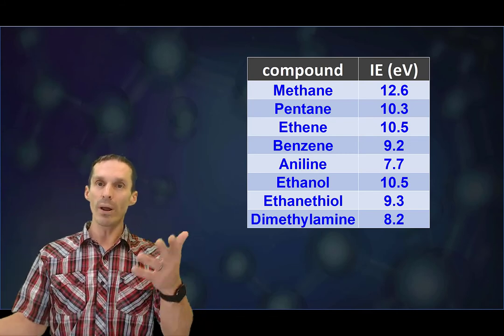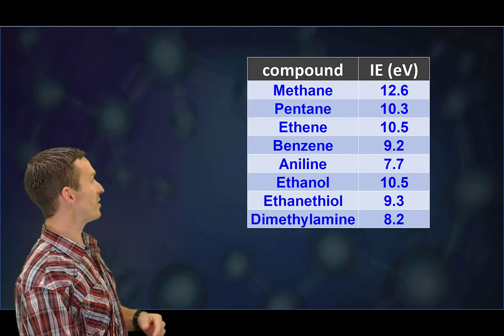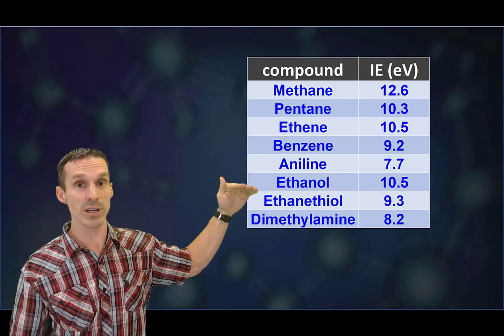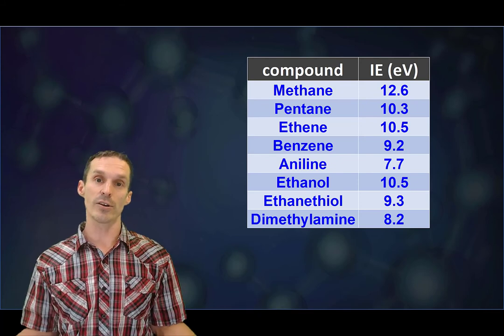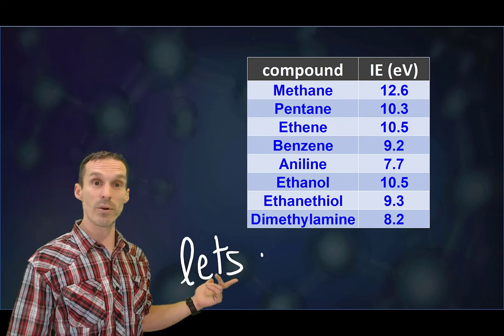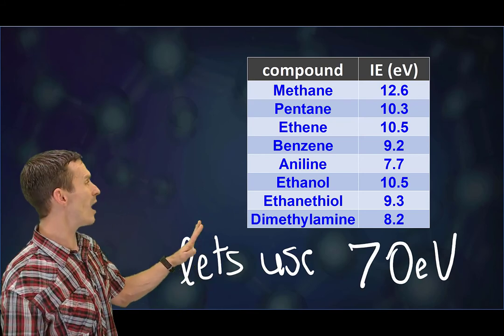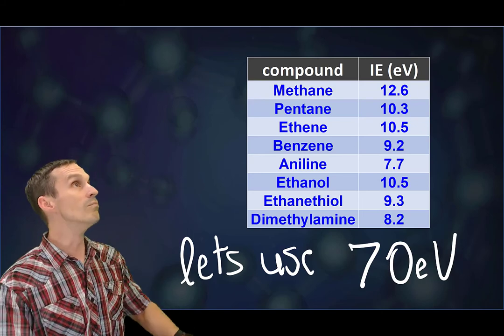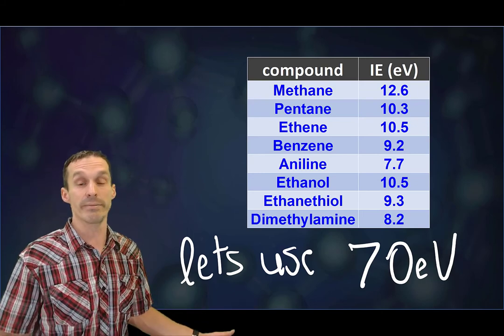Now let's ask, what energy should we pick? Based on all of these, let's make sure that it's at least that much. If you don't have that much energy, you're not going to have enough to ionize your compound. So we should pick at least that much energy. And in fact, the number that we pick is surprisingly high. We tend to pick 70 electron volts, more than enough to ionize everything.